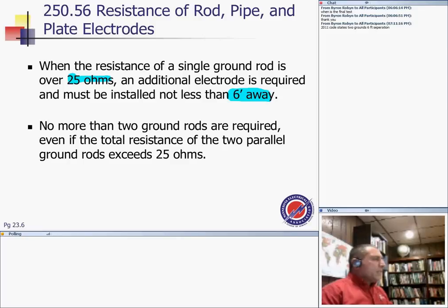In 2011, guys, they changed it to say the following. Now an exception: if you have a rod, pipe, or plate, you need two electrodes unless you prove that the resistance is 25 ohms or less. No more than 2 rods are required if the resistance is still more than 25.